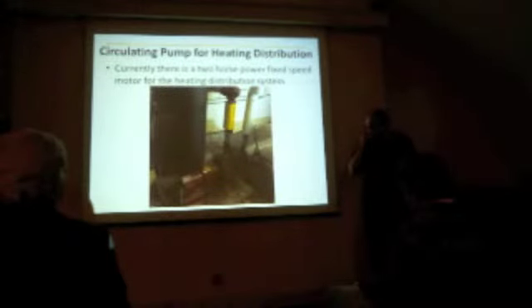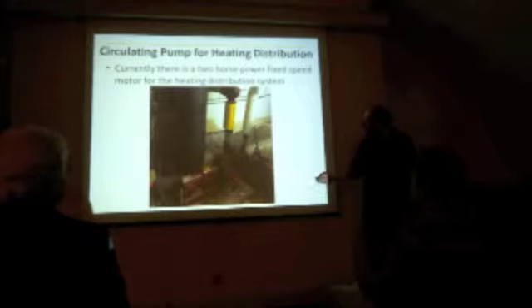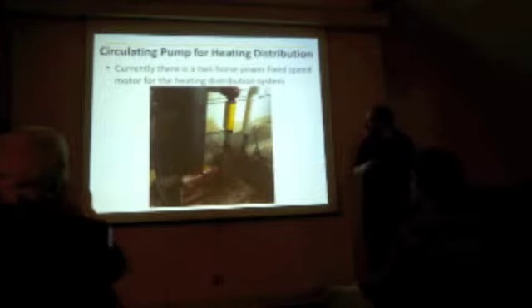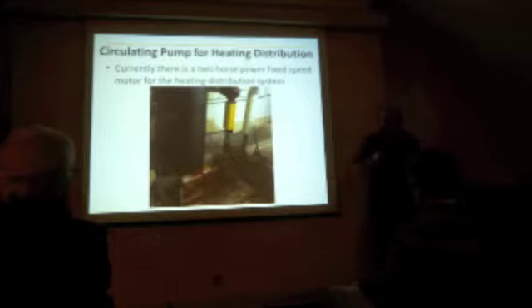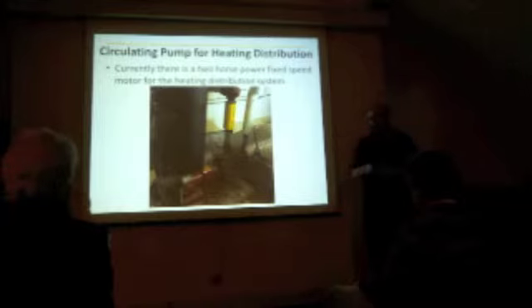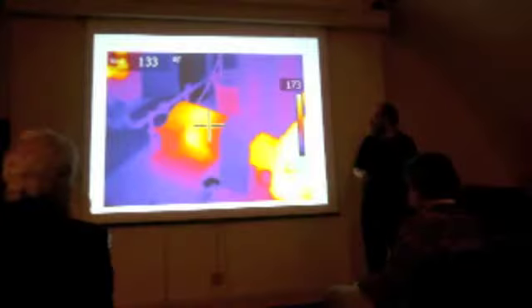Another place where electricity comes into the heating a little bit. Right now, the pumps that drive the heating supply, so this is the supply water here for the heat, is essentially just a little 2-horsepower motor that is on or off. It's not variable speed. It just turns on and pumps at a constant power regardless of how much heat is actually needed. And so particularly in the shoulder seasons, when some of the rooms will already be up to temperature and not need that heat, this will still have to run at full capacity.